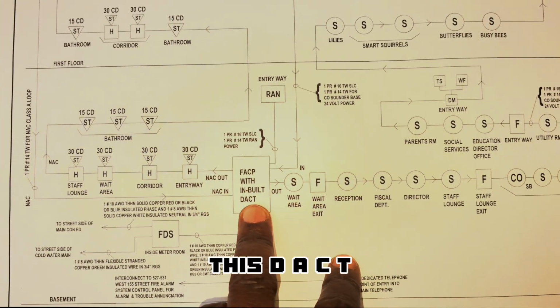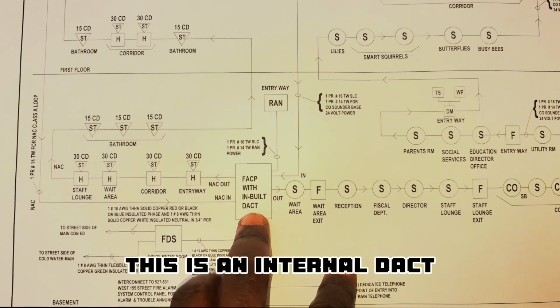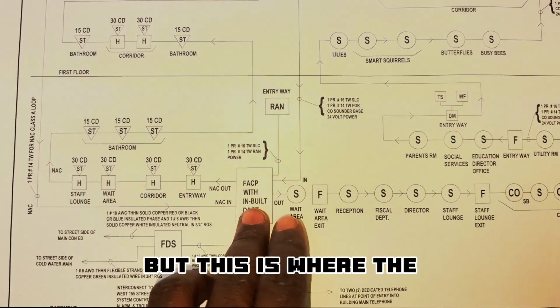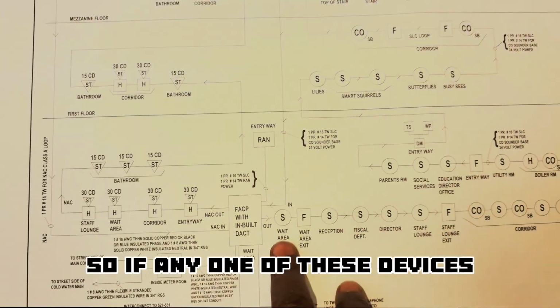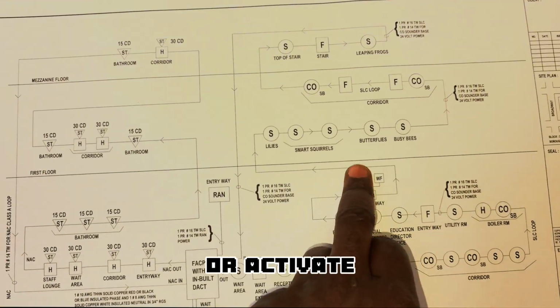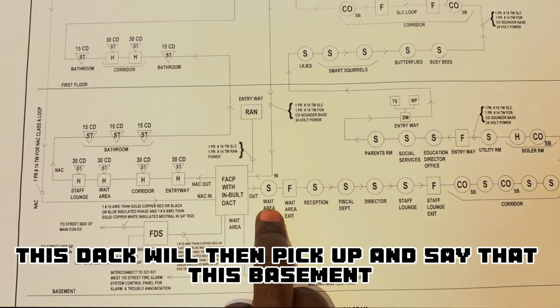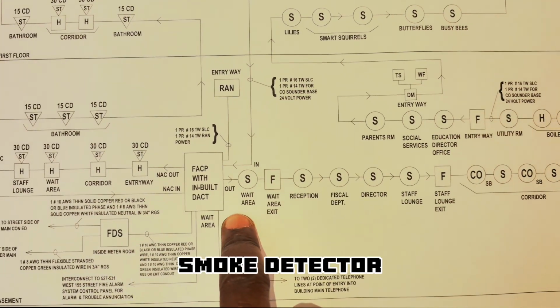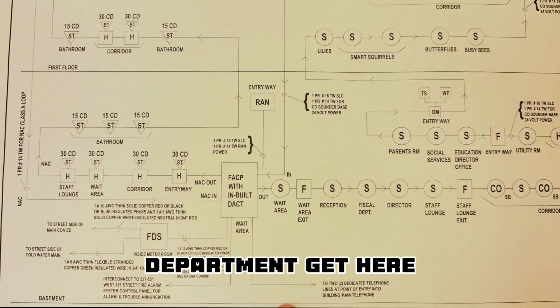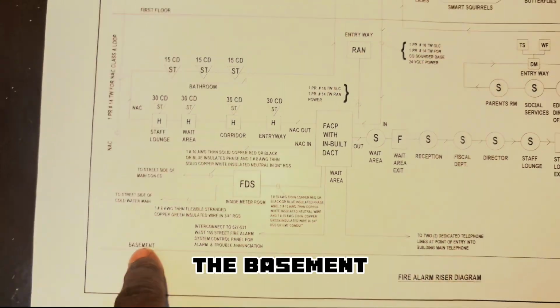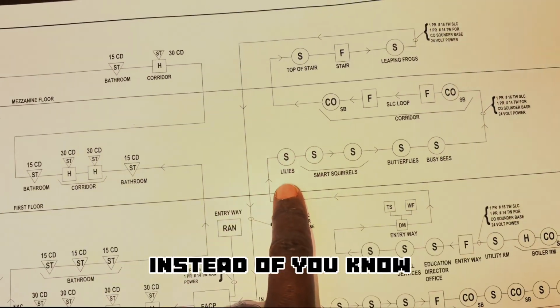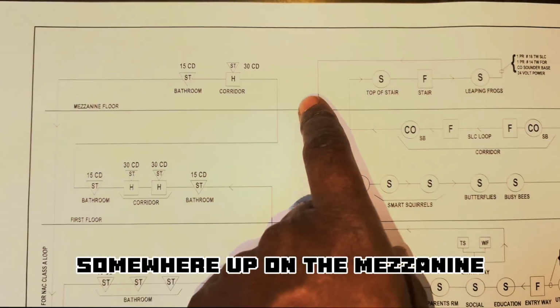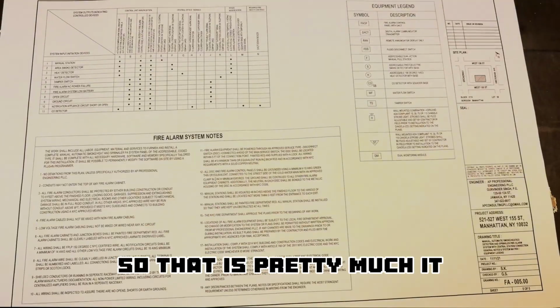This DACT is your dialer. This is an internal DACT, or it could be an external DACT, but this is where the phone lines would connect to. So if any one of these devices goes into alarm or activates, this DACT will then pick up and say that this basement waiting area smoke detector just went into alarm. So when the fire department gets here, they know to go to the basement waiting area instead of somewhere up on the first floor or somewhere up on the mezzanine. They go straight to where the source is. So that is pretty much it.